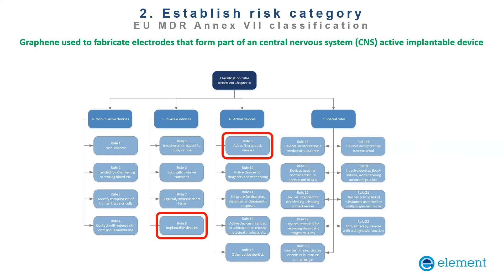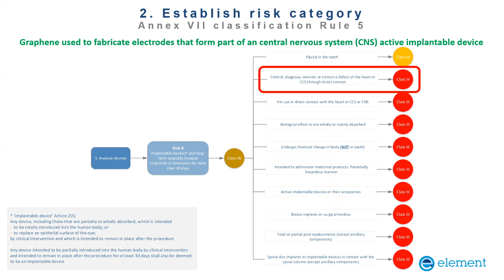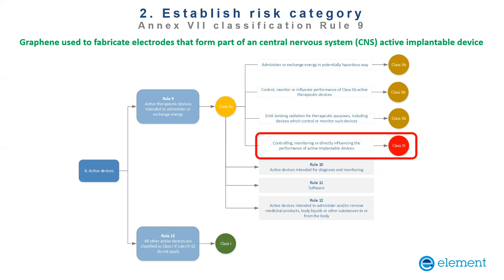If we look at Rule 8 in a bit more detail, so here we are. It's saying it's class 3. It's not a huge surprise. Just going through that very simple decision tree tells you, broadly speaking, what class your device is. If we look at Rule 9, again it's class 3. If one had said class 2A or 2B and one had said class 3, you always take the higher class. So as soon as you've got class 3, you're always going to be class 3, effectively.